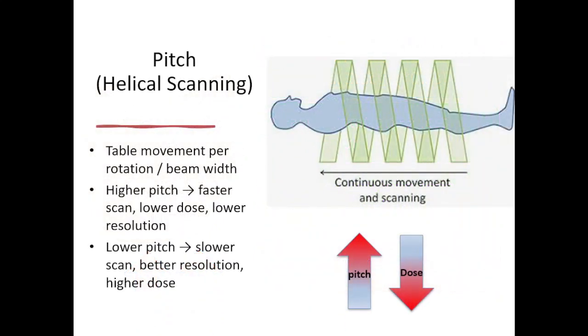Next is pitch, which is used in helical scanning mode. Pitch determines how fast the CT table moves relative to the x-ray beam. A higher pitch speeds up the scan and lowers radiation dose, but reduces image quality, requiring more interpolation for reconstruction. Conversely, a lower pitch provides better detail but increases dose. A pitch of 1 is equivalent to axial scan mode, ensuring full data sampling without gaps or excessive overlap.